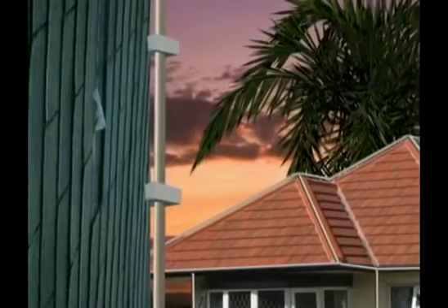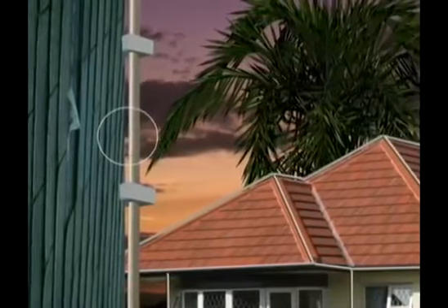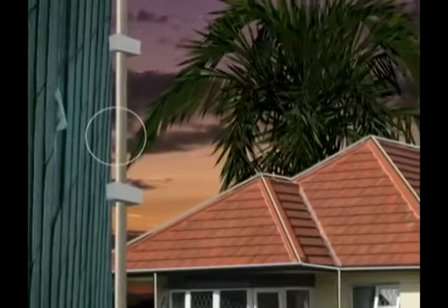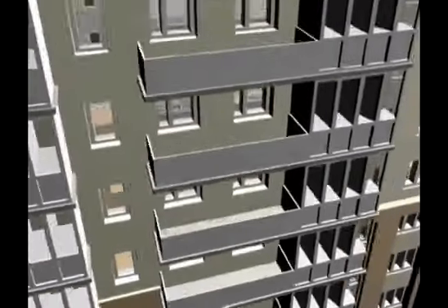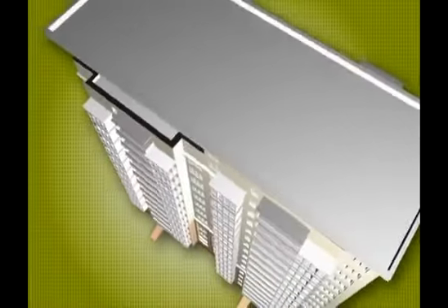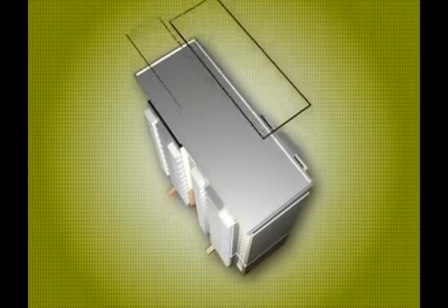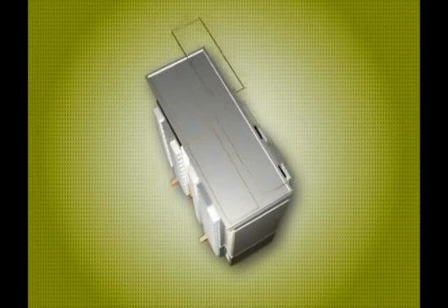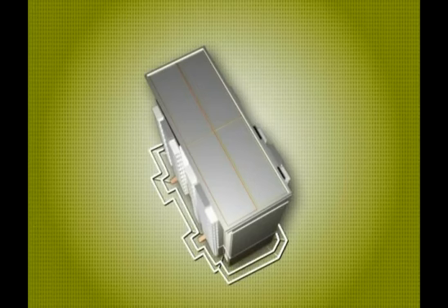When the down conductors pass through external walls made of flammable material, a specific distance needs to be maintained between the wall and the conductors. When the arrestor system is installed in high-rise buildings, it is to be ensured that down conductors are installed every 10 to 20 meters. When down conductors are placed parallel to the roof, they are to be linked using ring conductors to prevent fire outbreaks.